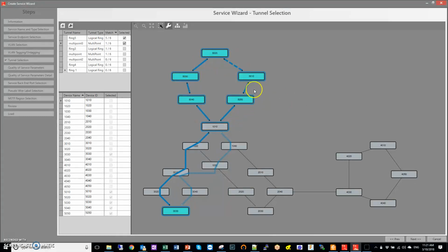And if anything happens on the other links there, each individual link here is protected by a BFD session. So a BFD from this point to there, here to here, here to there, and if anything happens, it will signal to the ERPS ring that this blocked port needs to be unblocked. And how fast that's going to be depends on how quickly you send the BFD session. It can be sub 50 millisecond. If you choose to have slower BFD, it'll be slightly slower, and that really depends on your application. For SCADA, you could probably afford to go a little slower.